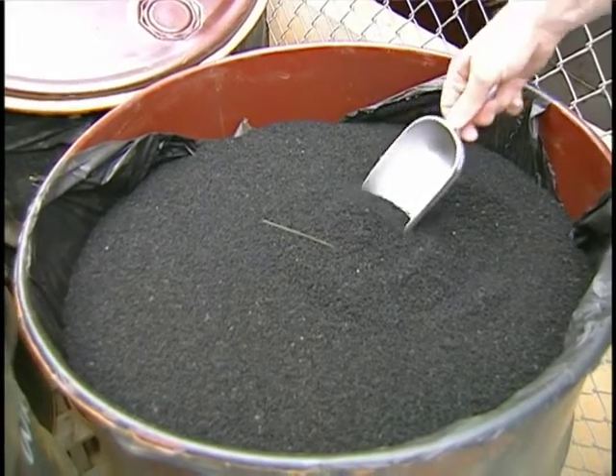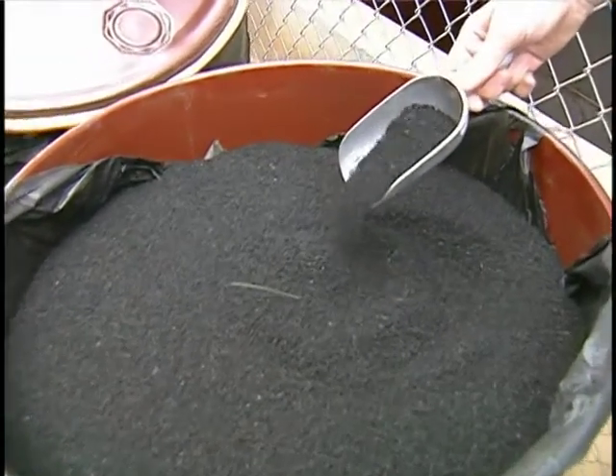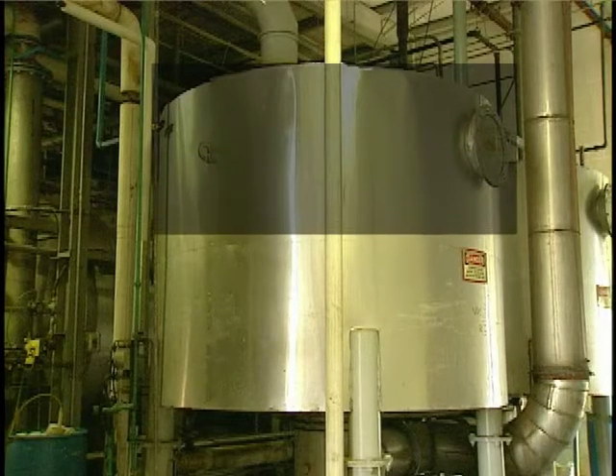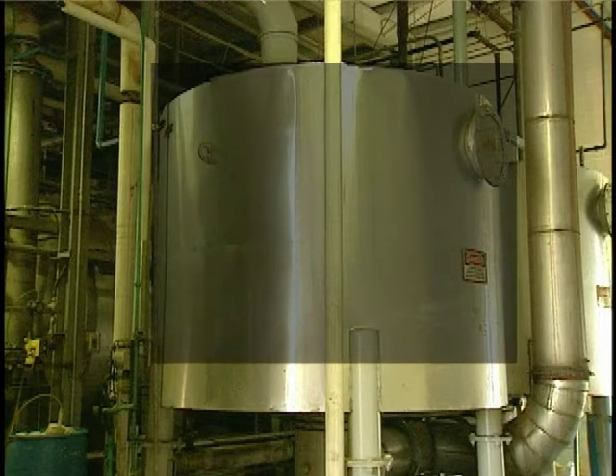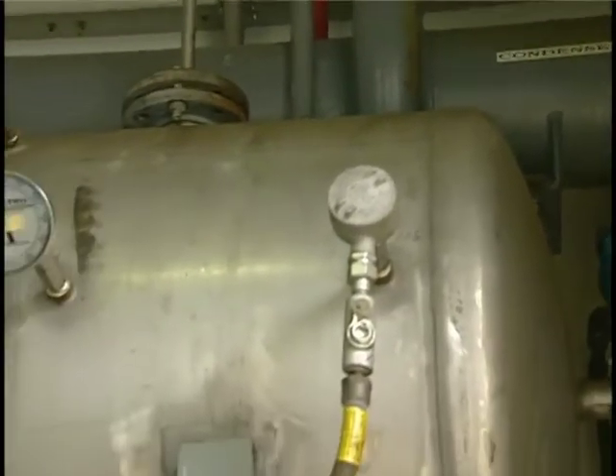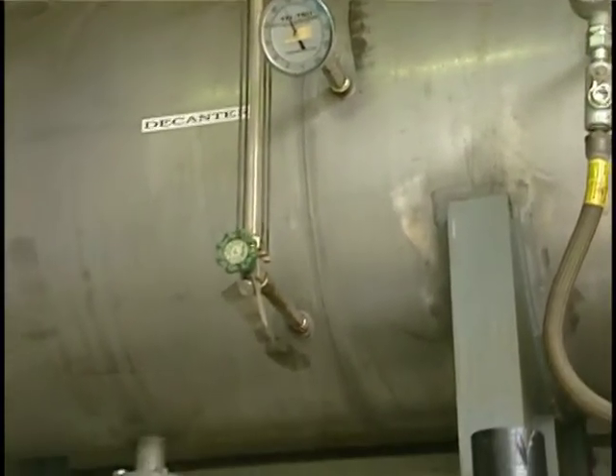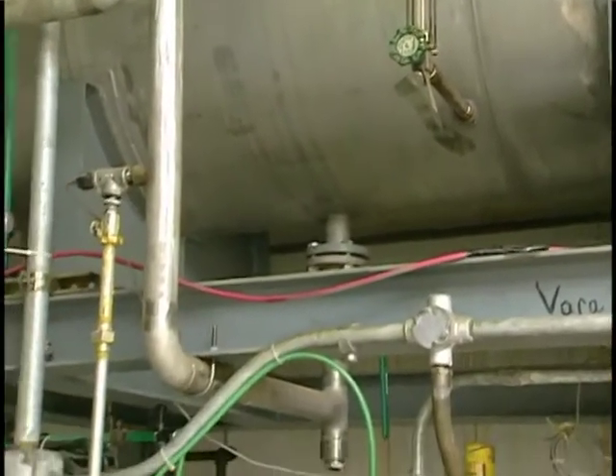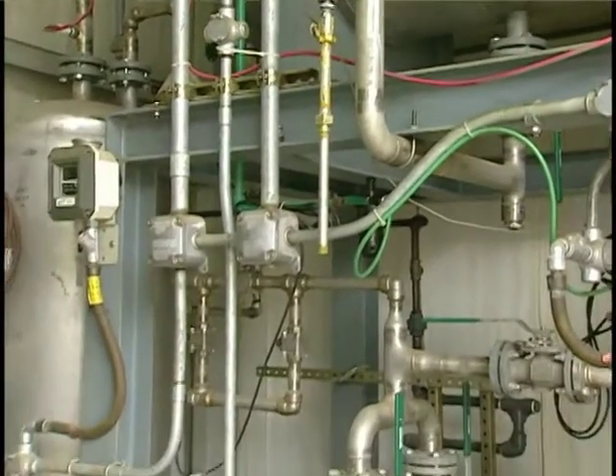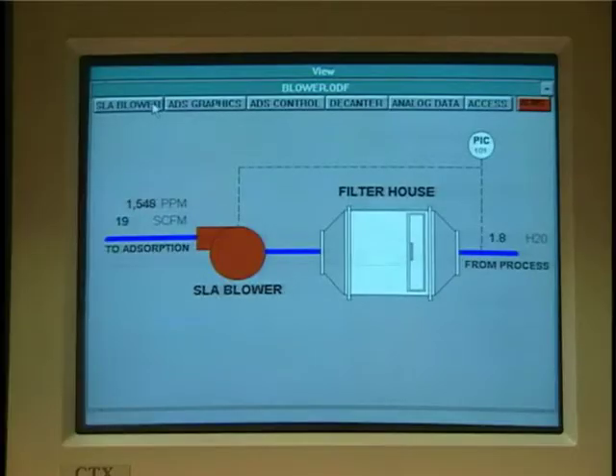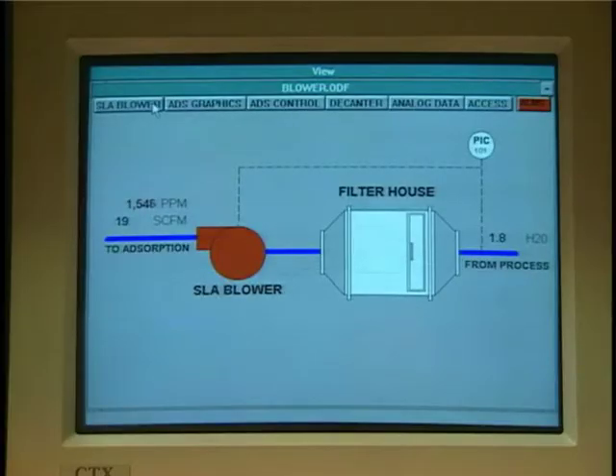Retention also increases as the organic concentration increases. However, more total carbon is usually needed at higher concentrations because of the greater quantity of organic contaminant that must be collected. Retention is affected by the molecular weight of the contaminant molecules; as the molecular weight increases, retention increases. Moisture in the gas stream can also affect retention, as water will adsorb onto activated carbon competing with the organic contaminant for adsorption sites. Since adsorption is also affected by the presence of liquid and solid particles in the gas stream, particulate matter must be removed before entering the adsorber.